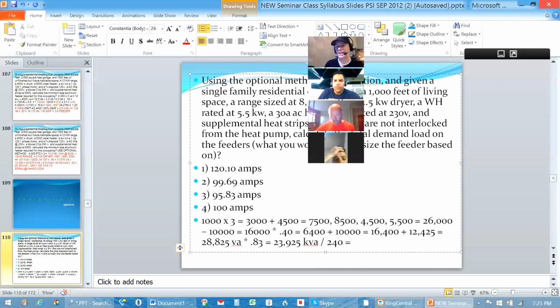That's 28,825, and I'm getting the 0.83 from 310.15(B)(7), the new multiplier that we have for residential feeders. The question is asking me to calculate the total demand load on the feeders, what I'd actually use to size the feeder. My calculated answer is 99.69 amps. Work the steps and see if you follow. The 23,925 was my total calculated value after I took the 83% for the residential dwelling. Divided by 240 volts, it gave me 99.69 amps.